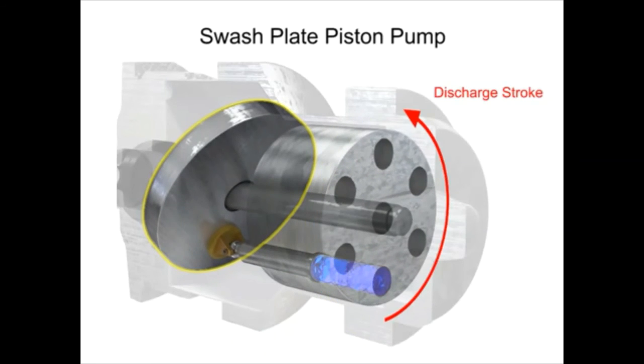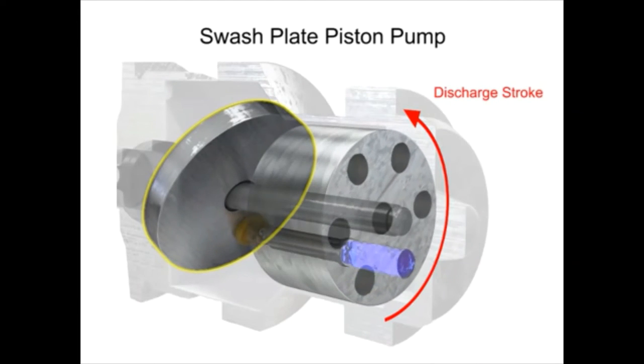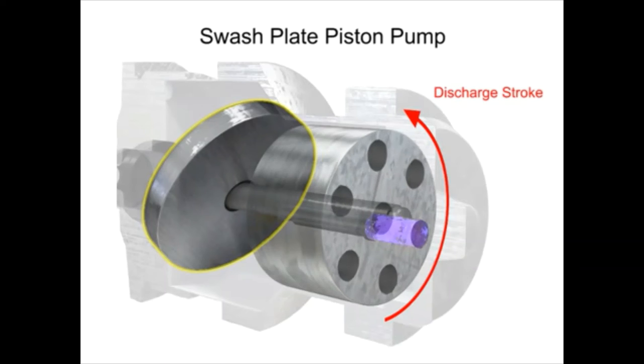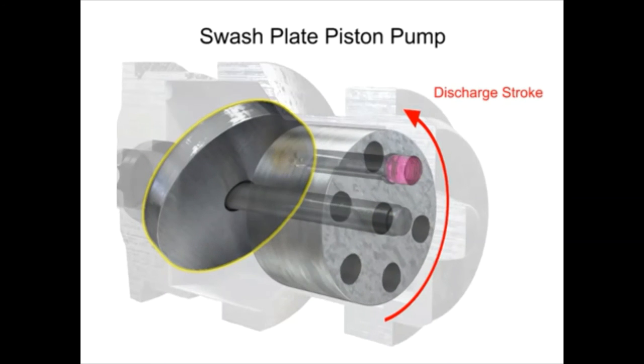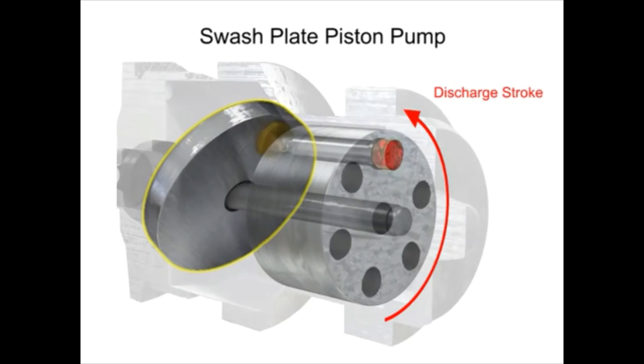On the discharge stroke, the angle of the swashplate forces the pistons back inside the piston block and discharges the fluid. The greater the slant on the swashplate, the further the pump pistons move and the more fluid they transfer.